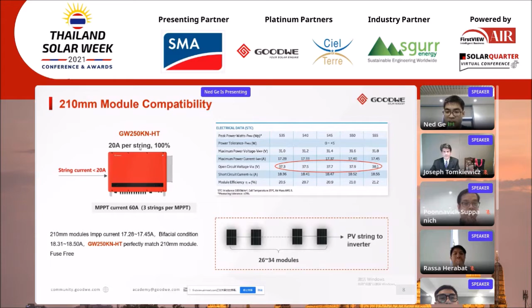With the 3-string design in one MPPT, most clients may have the concern whether they need an extra fuse to prevent the 2 strings' current from backfeeding to 1 string. Well, the KN still utilizes the non-fuse design to solve this problem, and it is equipped with an intelligent DC switch which can automatically trip when an overcurrent failure occurs. The DC switch can receive the trip signal from the inverter DSP to shut down the DC circuit in an emergency. And you have to check the trip signal and use the reset switch to recover the system. The switch is also rated to break the short circuit current of the DC circuit when it receives the trip signal from the DSP. And this is the way we solve the large DC current protection in the 3 strings in one MPPT design.